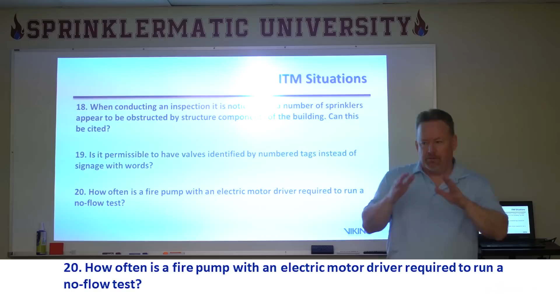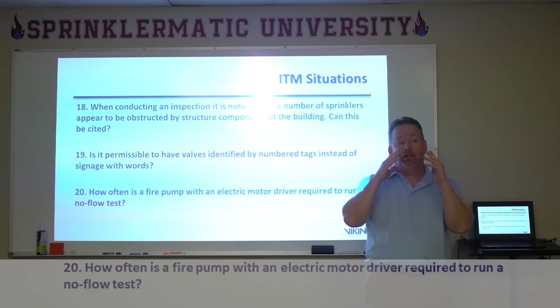How often is a fire pump with an electric motor driver required to run a no-flow test? So, fire pumps annually require a flow test. But on another frequency, we have to do what we call a churn test, or no-flow test, where they just run for a certain amount of time and then stop.